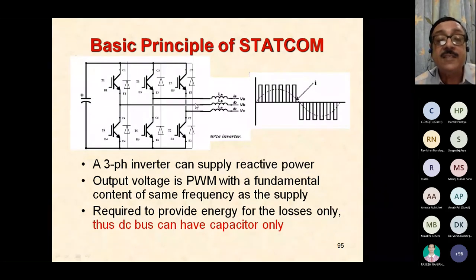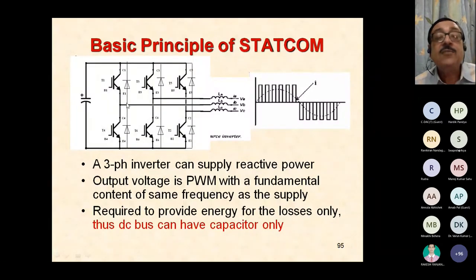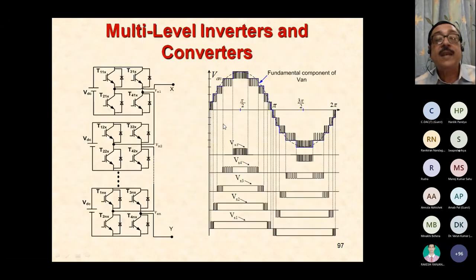There are losses in the system, which will drain out energy in the capacitor, both in this as well as the active power filter. So what you have to do is ensure a little bit of fundamental current flow into this to maintain the bus voltage. If you are able to maintain the bus voltage to the required value, then your operation continues. So from the grid, you have to draw a little bit of power to maintain that bus voltage. That is the catch.